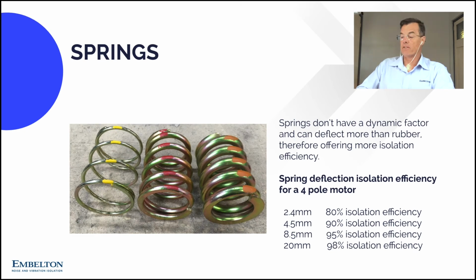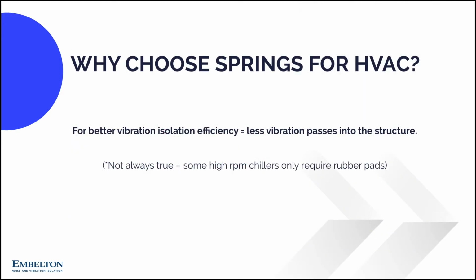Springs don't have a dynamic factor and can deflect a lot more than rubber, so can offer a much higher degree of isolation. But you can see here, deflecting a spring 20 millimeters offers 98% isolation efficiency for that 4-pole electric motor. And that's why we choose springs for HVAC. In critical applications, less vibration passes into the structure.